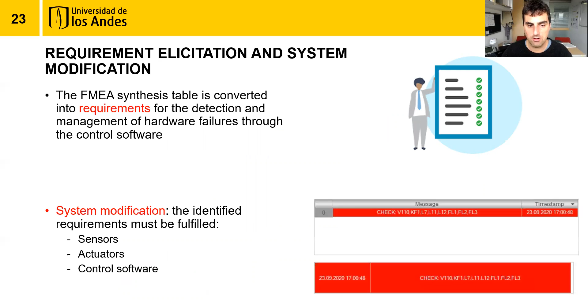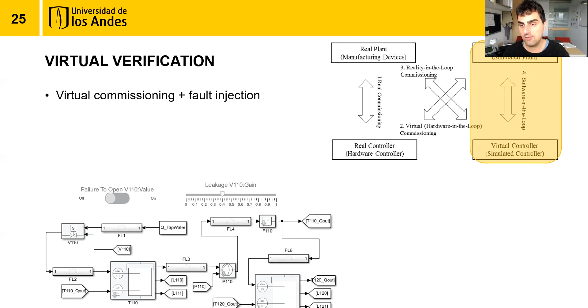Then eventually we have the virtual verification, where we propose the integration of virtual commissioning and fault injection. In our case, we built a software-in-the-loop simulation by integrating a Simulink kinematic model of the filter unit with the Codesys PLC programming environment, adding buttons and gauges to inject faults and study the software's reaction to them. Eventually, the control software is deployed once its modifications and the integration of additional sensors and actuators have been verified through the described virtual environment.